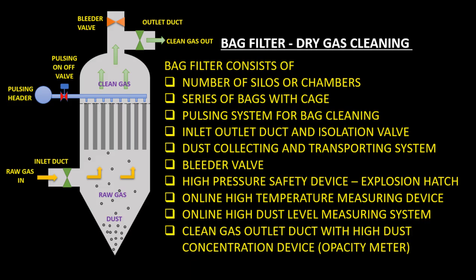Bag filter used for dry gas cleaning plant consists of a number of silos or chambers to hold raw and cleaned gas inside, a series of bags with cage to separate dust from gas, a pulsing system to clean the bags periodically, and inlet/outlet ducts with isolation valves for taking a chamber online or offline.